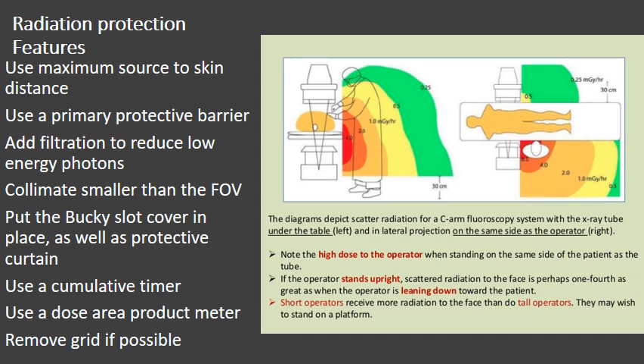So here are some other radiation protection features that are incorporated to keep patients and the occupational worker safe. The source to skin distance of the X-ray tube needs to be 38 centimeters or 15 inches minimum. mA increases as the distance between the source and the IR increases. This is the inverse square law applied. So in examples, if the source skin distance increases from 20 centimeters to 40, which is doubled, on a 20 centimeter thick patient, the entrance skin exposure decreases from 128 milliroentgens to 72 milliroentgens.